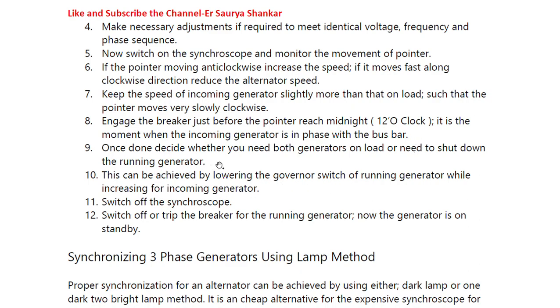Once the breaker is engaged, decide whether you need both generators on load or need to shut down the running generator. This can be achieved by lowering the governor switch of the running generator while increasing it for the incoming generator. All these things are now automatic, but it is important to understand the concept. Switch off the synchroscope, then switch off or trip the breaker for the running generator. The running generator is now on standby.